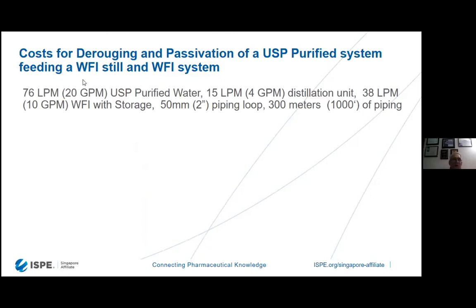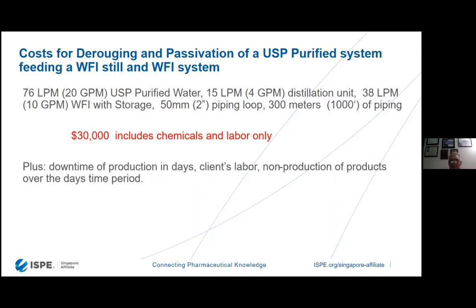So if we're looking at a fairly small system running at 76 liters per minute, or 15 liters per minute in the distillation unit, going out to a 38 liter per minute WFI water in storage with only a 2-inch piping loop running about 300 meters, what is the real cost of doing derouging passivation, even on this smaller system? Well, the actual cost in dollars, including chemicals and labor only, is about 30,000 US dollars. If you add in downtime of production in days, the client's labor, the non-production of the products because the system is down and can't produce product over that time period, it can get very expensive very quickly. For a small system, we're talking about $50,000 and higher.